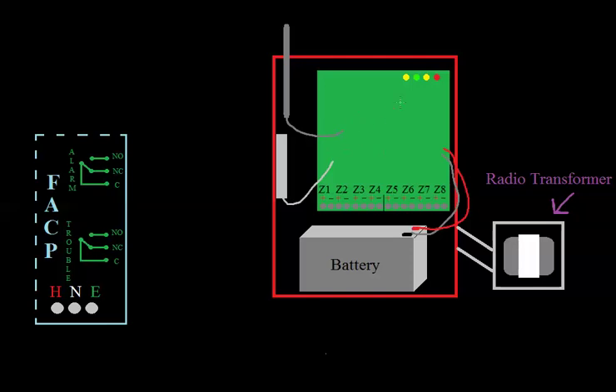So, on this radio, there's a couple different things. There's a couple different lights. One of these yellow ones, and there's a yellow and a green that's like a transmit and a receive. They'll both blink when there's a signal coming in. There's a waiting light, which if you're not able to, if it's not communicating with the central receiver, if it's not getting like a sign-off or whatever, not a sign-off, but like feedback from the central receiver, this waiting light will come on, or it will blink depending on the severity of it. And then there's this little alarm light, which will blink if there's a zone in alarm or trouble. But the main thing I want to show you are these zones. There's zones 1 through 4 on the left here, and then there's zones 5 through 8 over here on the right.